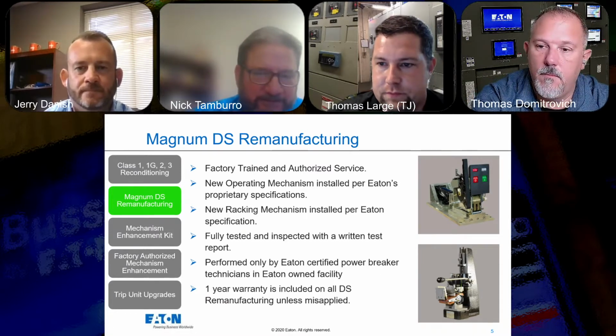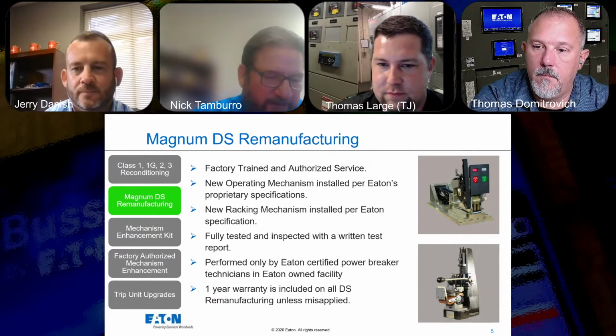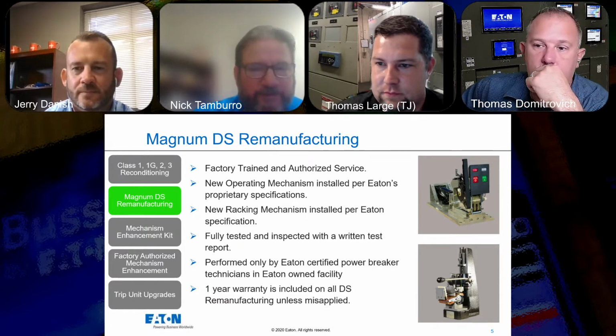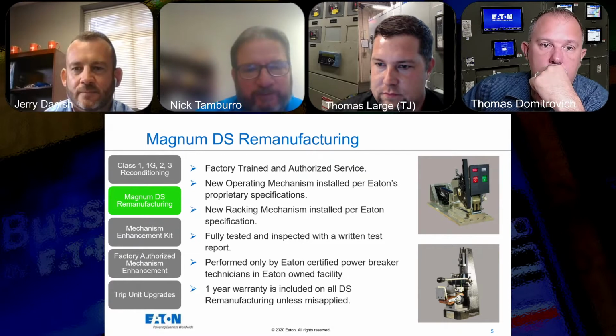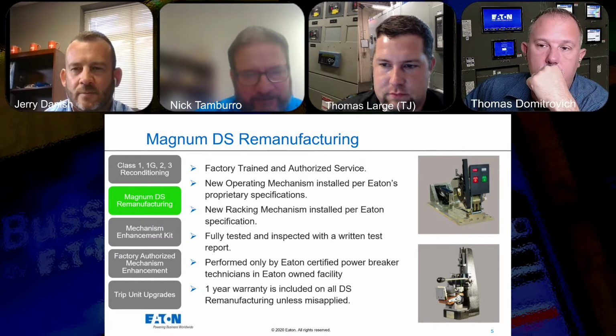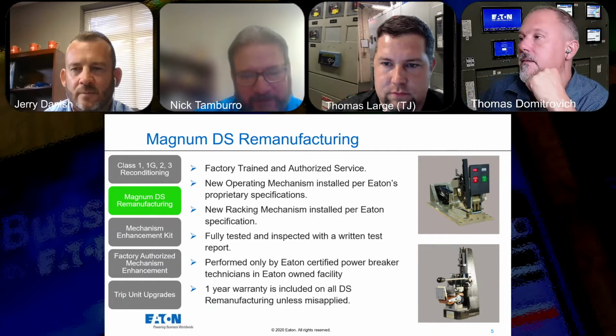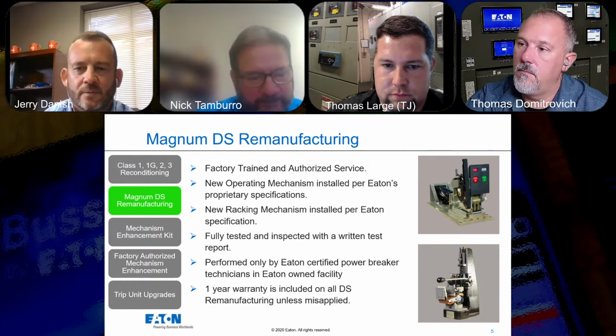A lot of customers will retrofit the breaker to upgrade to a more modern trip unit, and when they send it in for a class three, they'll send it to the PBRC so we can fully test it when it's done. So we do the class three here and install the retrofit kit.